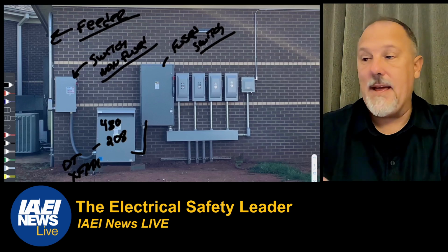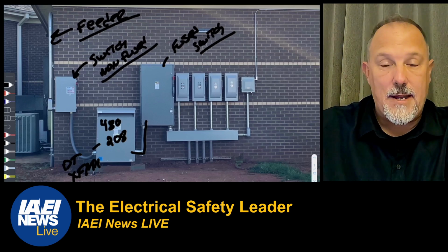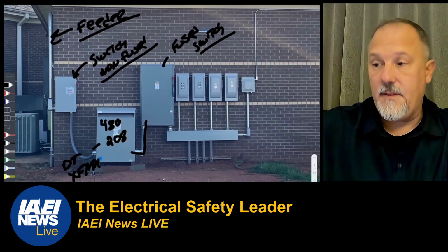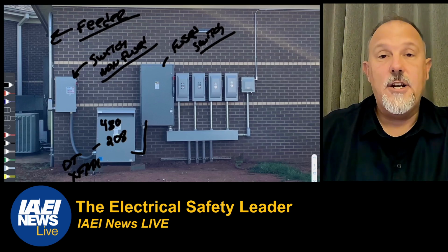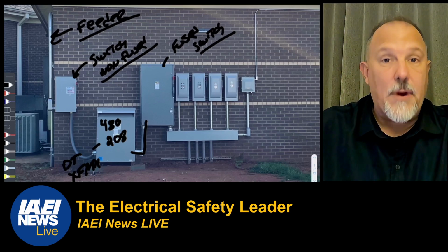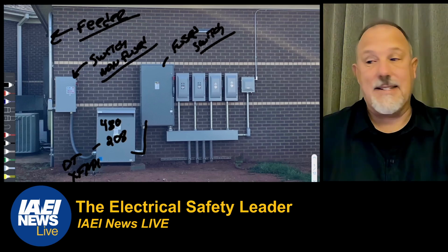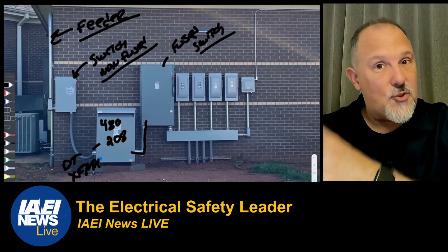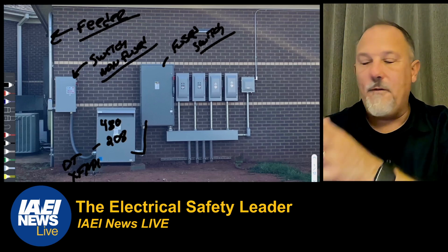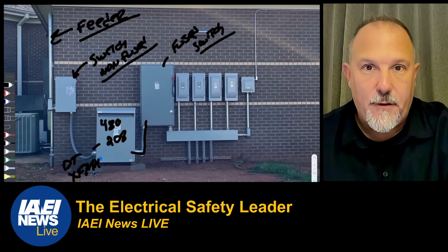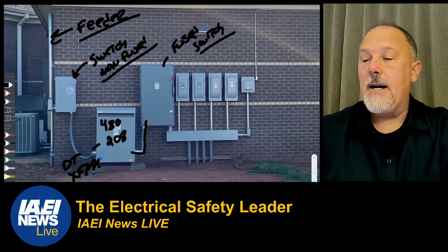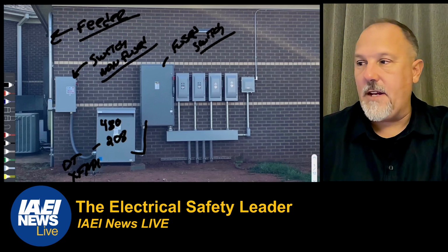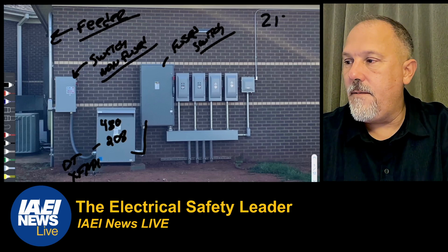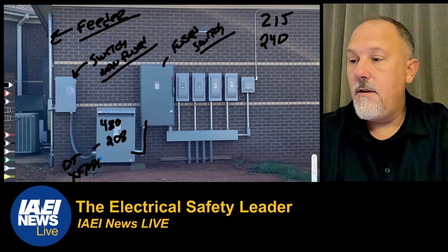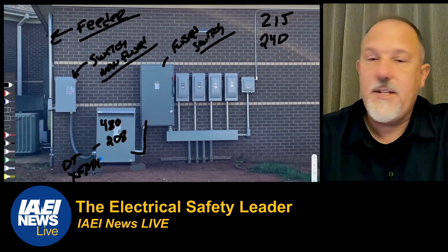Then on the primary, that breaker that's over there in the service panel that's feeding this transformer through that safety switch, you've got to figure out what size of breaker is that main breaker on the line side. So you have basic fundamentals of transformers. Article 450, you're in 215 for feeders, right? You're in Article 215 for feeders. So we have 215.